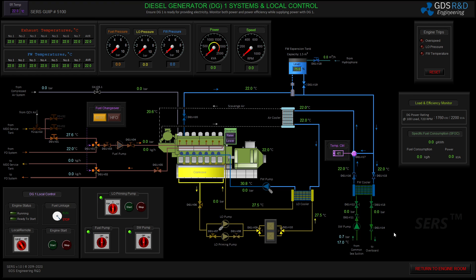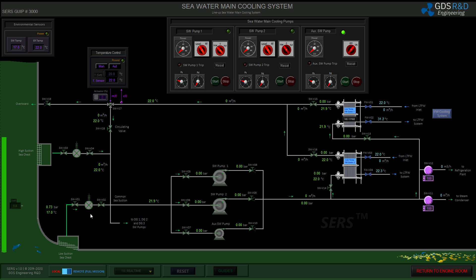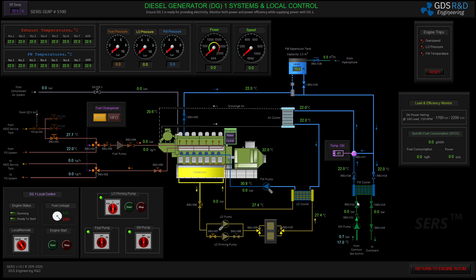I will line up the cooling system. I will start with the sea water system. I'm opening the sea chest to be able to supply sea water to the diesel generator, and opening inlet and outlet valves of the cooler and the overboard valve of my sea pump. My sea water line is now ready. I will switch to the fresh water line.